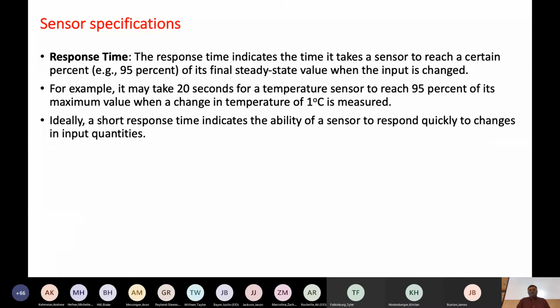The other important part is the response time, because obviously response time is going to be important. If you use a sensor and it takes 2 hours to get the result, that may not be of advantage. So you want that response time to be quick enough so that you can get the value. Response time indicates how much time it takes for a sensor to accurately reach the steady state and give the number that you need. So for example, it may take 20 seconds for a temperature sensor to reach 95% of its maximum value when you change the temperature by 1 degree. What that means is that you change the temperature by 1 degree, and within 20 seconds, the value that you get is 95%.